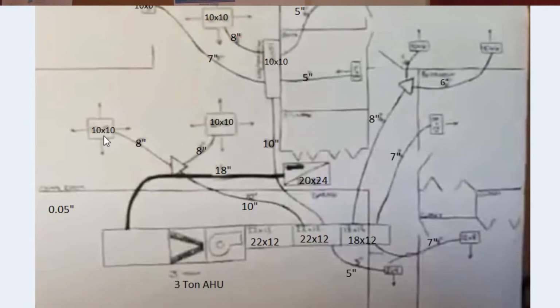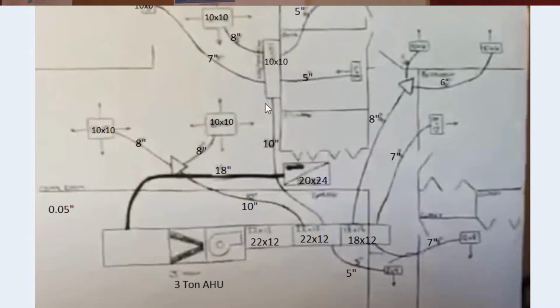Okay, so then we add that into the equation. So now we're at the air handler, 0.5, minus the 0.03 on the damper, minus our ceiling diffusers at a 0.031. Okay, so that is our supply side pressure drop.